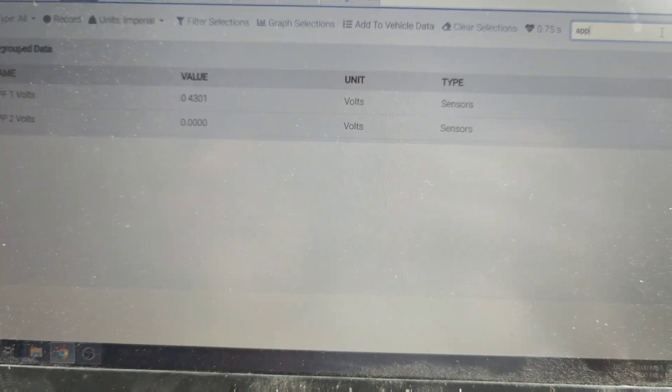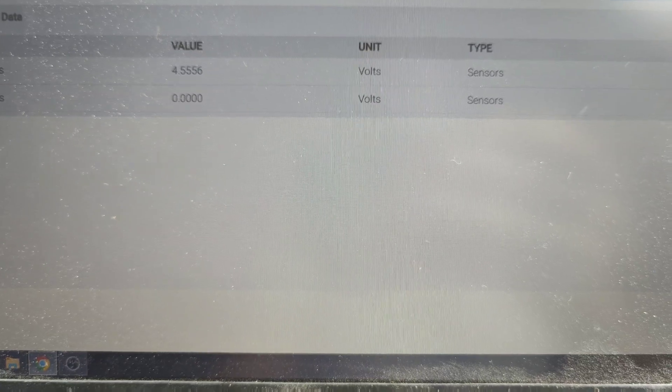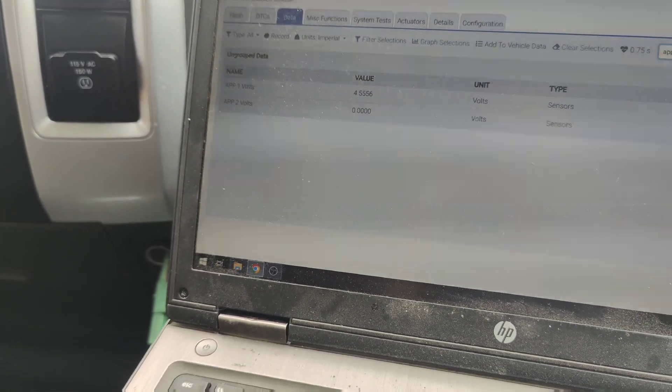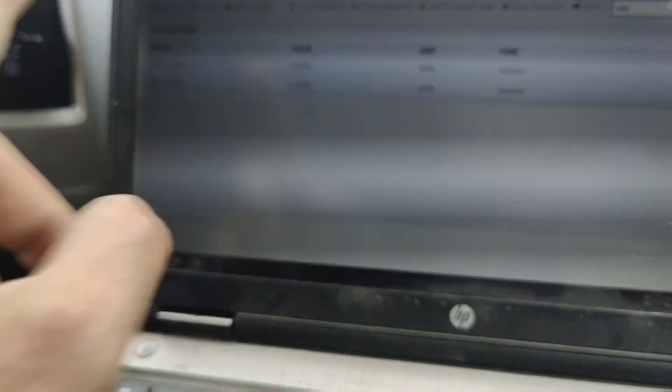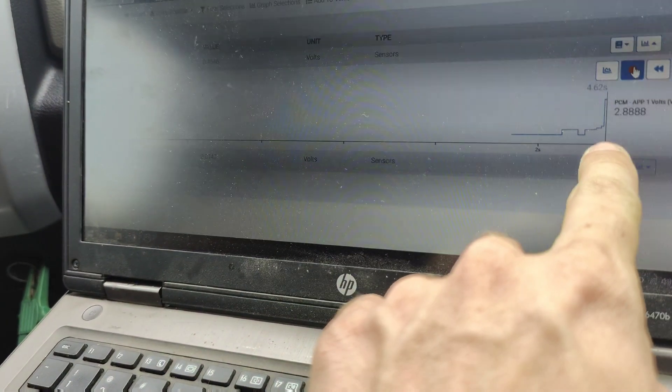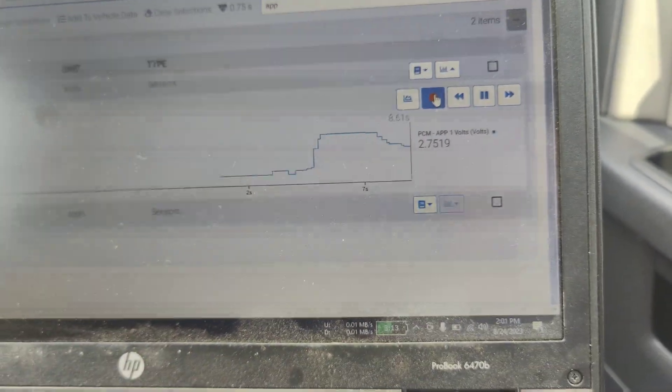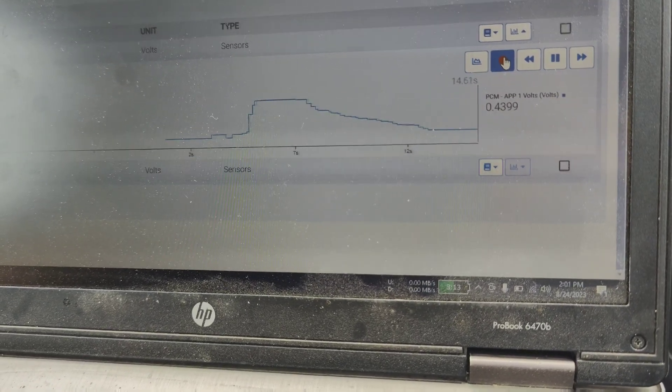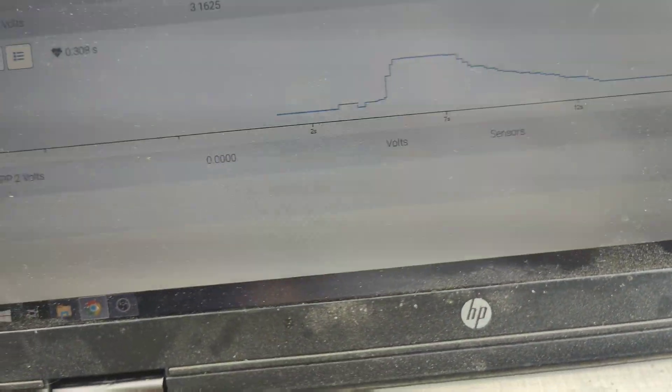All the way? Yeah. So that one goes with the 4.5, but if you let it out partway does it? It goes down. But that's weird because we had it on this other one before. Well, we're not on the signal return, we're only on... We said we had a bad ground. We don't know if we have a good... Yeah well, we jumped the ground right there in your hand. But why is APP2 now at 0? So now it's showing a little bit. Because now our APP is working. Like it's actually moving when you do that. Oh, go to my... see that? Move it slowly and you'll see... Look, see? It's working now.